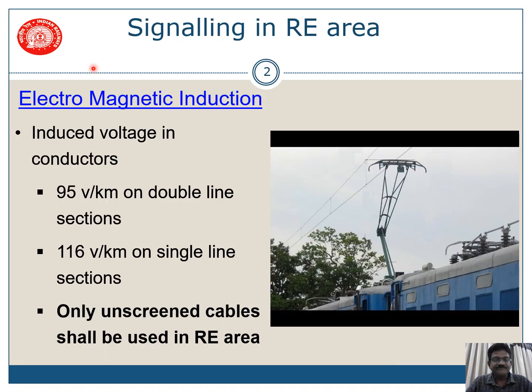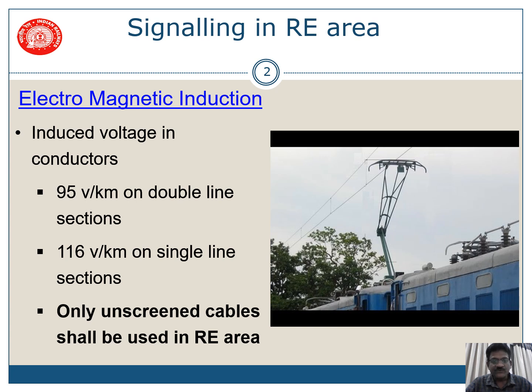The induced voltage in conductors, as we have seen in Part 1, is 95 volts per kilometer on double line sections and 116 volts per kilometer on single line sections. As we have already seen, only unscreened cables shall be used in RE area. In unscreened cables, even though earthing of cable armor is not proper, we should not have any unsafe condition in our signaling system. To ensure that, we have to have some restrictions.